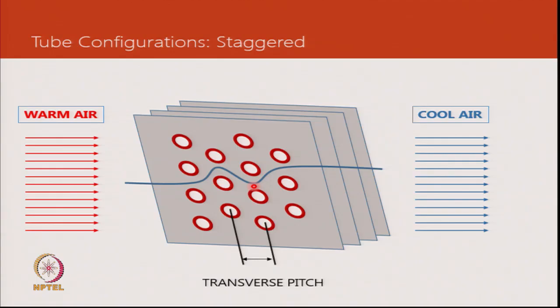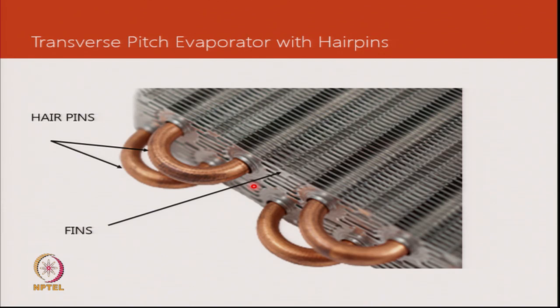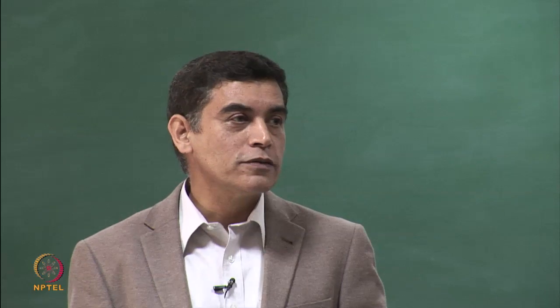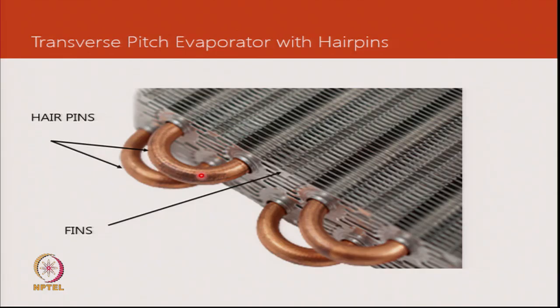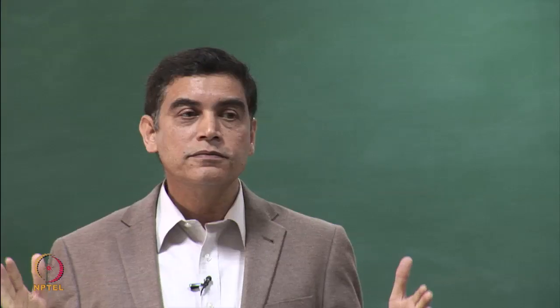Looking at a physical coil, we can see the fins before it is fully manufactured. One task is to define the gap between fins — whether 2 millimetres or 5 millimetres; conventionally the number of fins per inch is specified. These tubes are referred to as hairpins because a long tube is bent and folded automatically, eliminating connectors on one end of the heat exchanger.